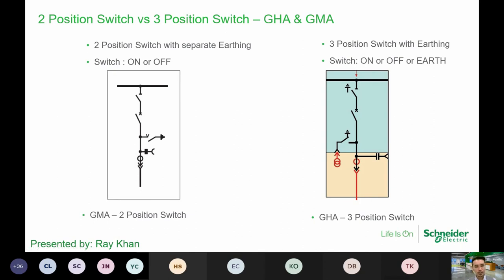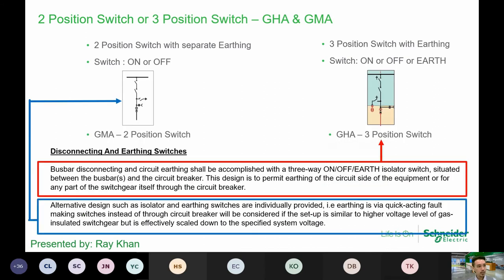Just to share, both technologies are tested according to IEC standards. The IEC standards don't specify that it must be a two position or three position switch, because these two concepts are tested and accepted by IEC 62271. So that is why for the bus bar disconnecting system, they have a statement that points to a three position switch, and we also recommend having a statement for alternative designs, such that the isolator and earthing switch can be individually provided.